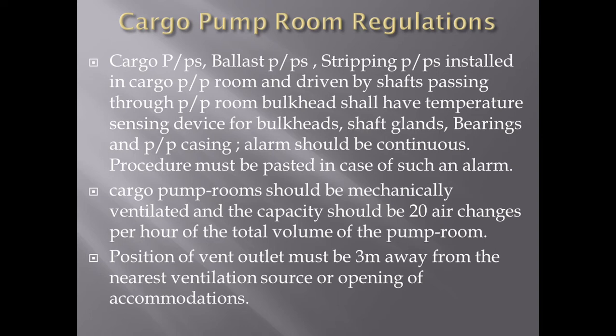The cargo pump room should be mechanically ventilated, and the capacity should be 20 air changes per hour of the total volume of the pump room. The position of the vent outlet must be three meters away from the nearest ventilation source or opening of the accommodation. These ventilation regulations are important because of the flammable, toxic, and fatal gases that may come out — if it goes into accommodation, that will also be fatal.